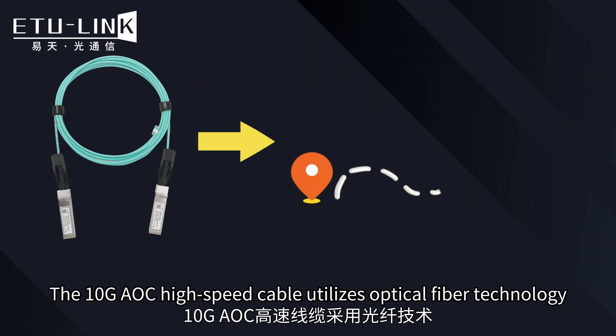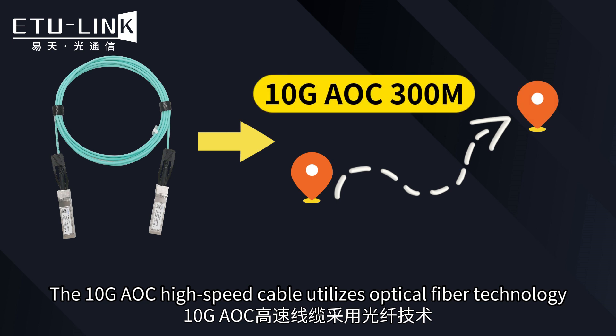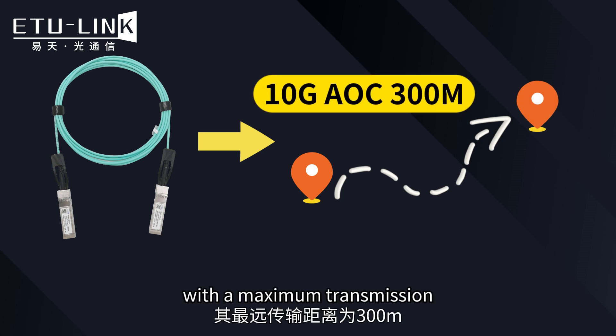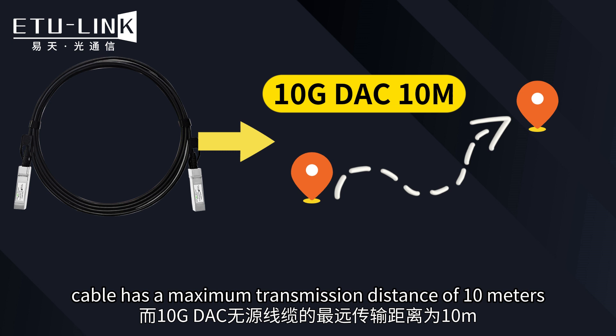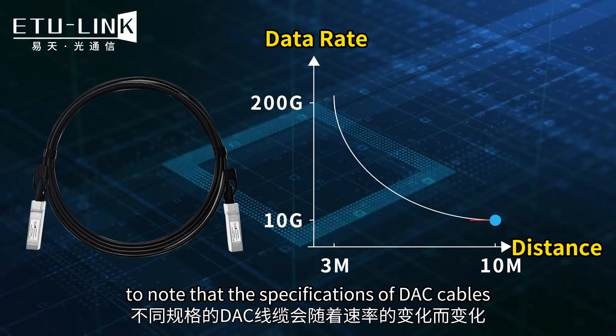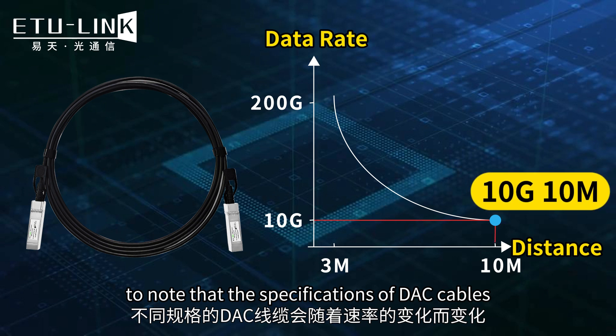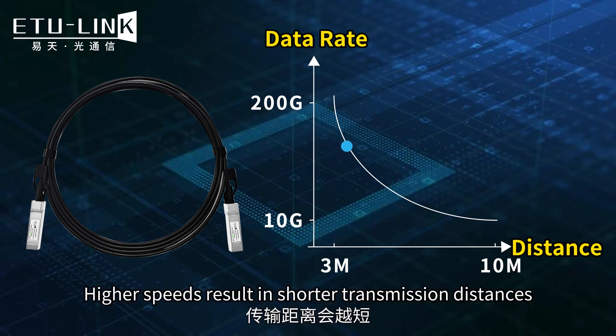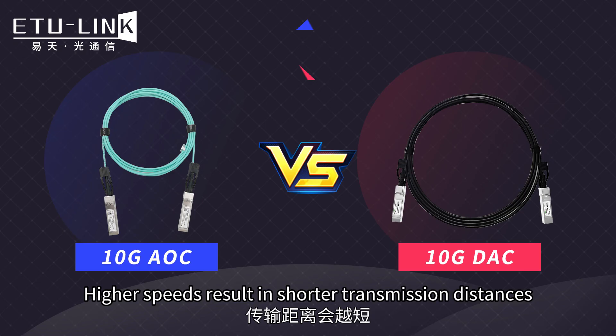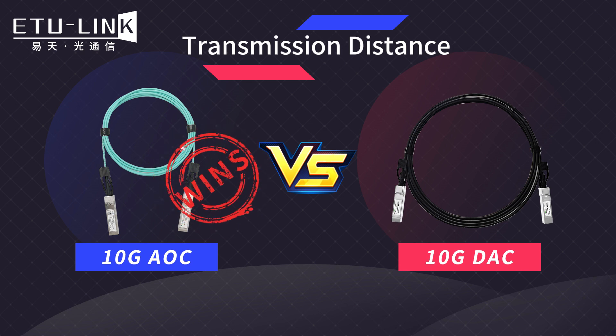The 10G AOC high-speed cable utilizes optical fiber technology, with a maximum transmission distance of 300 meters, whereas the 10G DAC passive cable has a maximum transmission distance of 10 meters. It is important to note that the specifications of DAC cables can vary depending on the speed — higher speeds result in shorter transmission distances. For transmission distance, 10G AOC wins.